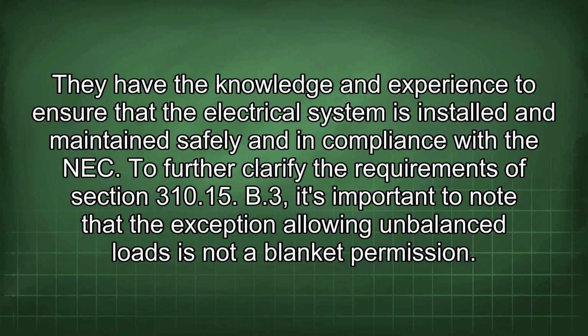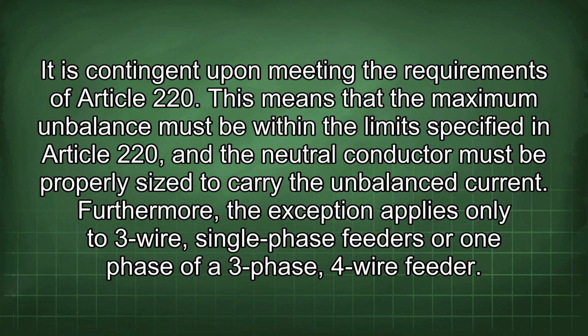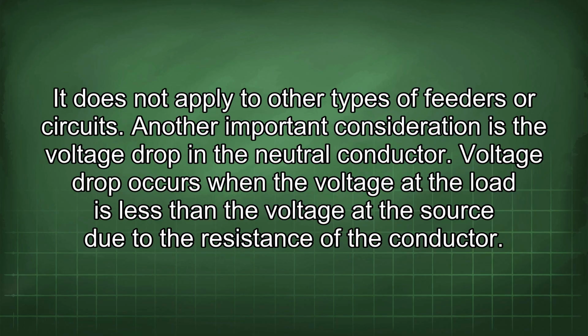To further clarify the requirements of Section 310.15, it's important to note that the exception allowing unbalanced loads is not a blanket permission. It is contingent upon meeting the requirements of Article 220. This means that the maximum unbalance must be within the limits specified in Article 220, and the neutral conductor must be properly sized to carry the unbalanced current. Furthermore, the exception applies only to 3-wire, single-phase feeders or one phase of a 3-phase, 4-wire feeder. It does not apply to other types of feeders or circuits.